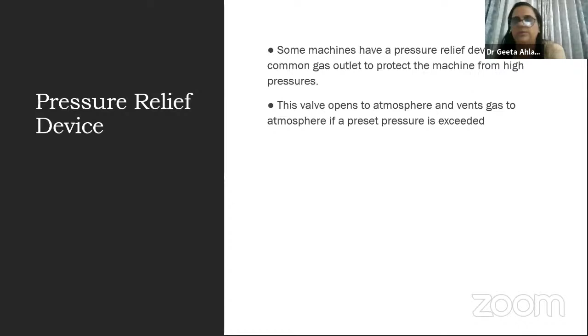This was very clearly evident in the older Boyle's machine and is not seen there. However, it is present in the newer machines. The common gas outlet is the exit point of all gases and vapors. It has a gas pressure of about 4 to 8 psi, and we all have a tendency of taking this common gas outlet, I think, as the most taken-for-granted part of the machine.